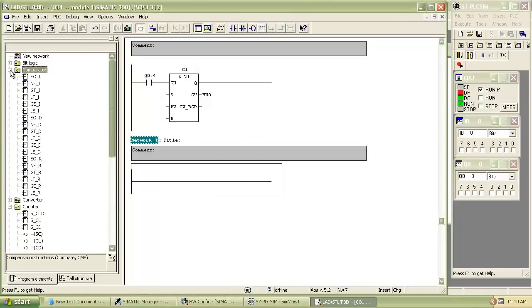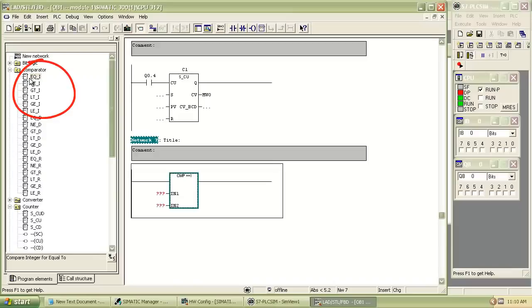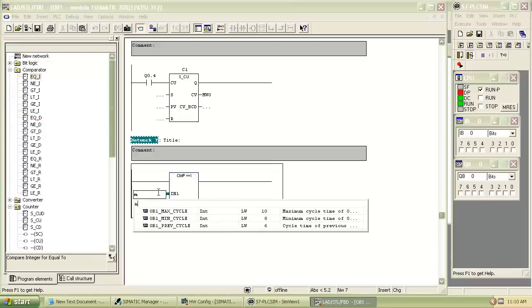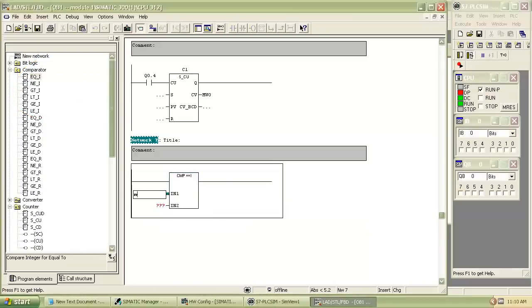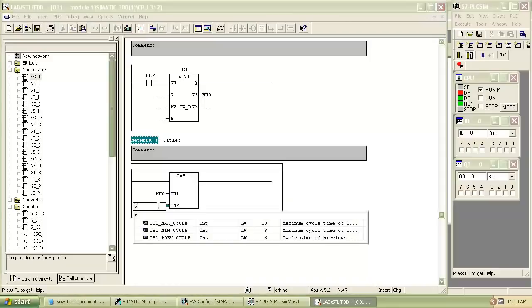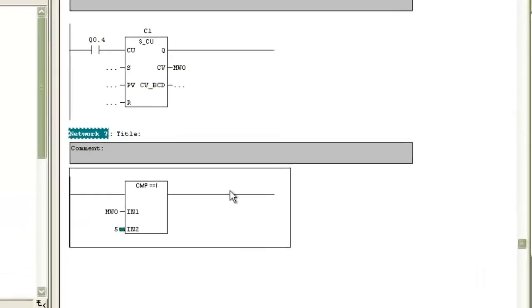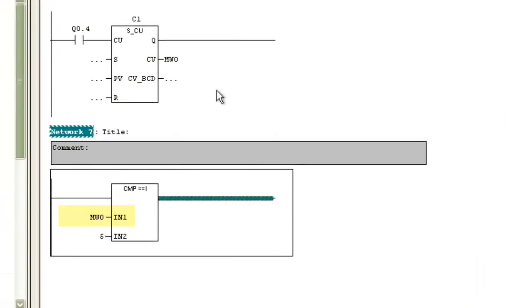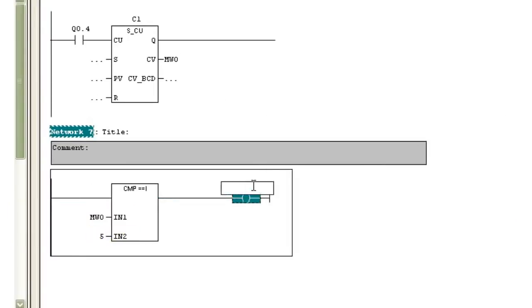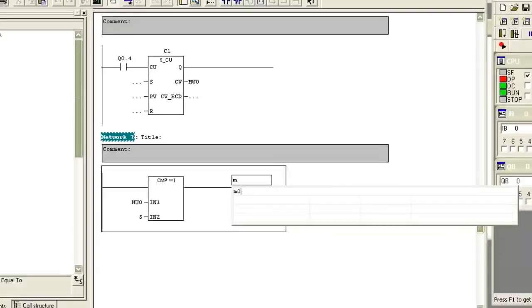Insert the comparator from program element under the tab comparator. Select equal value comparator, which means when value to be compared and given value become same, output will switch on. IN1 and IN2 are the two values for comparison. When these two values are equal, output switches on.